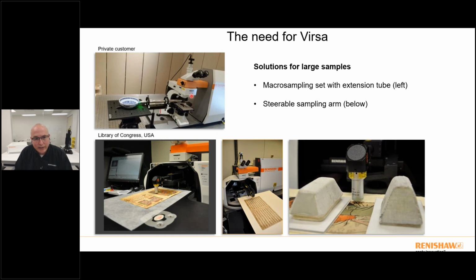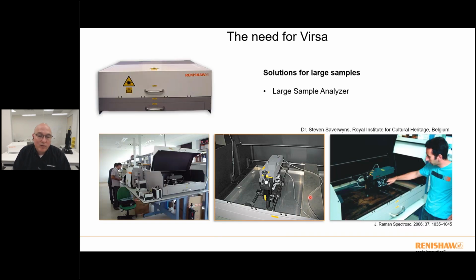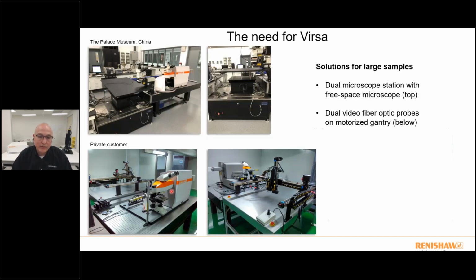So in this case, we have a simple turning mirror with an extension tube to look at large objects. We also have a steerable sampling arm, which can be used to motorize the position of an objective above a sample. We've also built large boxes with fiber optic probes in them, having video where you can position the laser delivery optics and the Raman collection optics right above your sample in very large samples that way using fibers. And then we've also done things like dual microscope stands and large gantries with video probes on them.